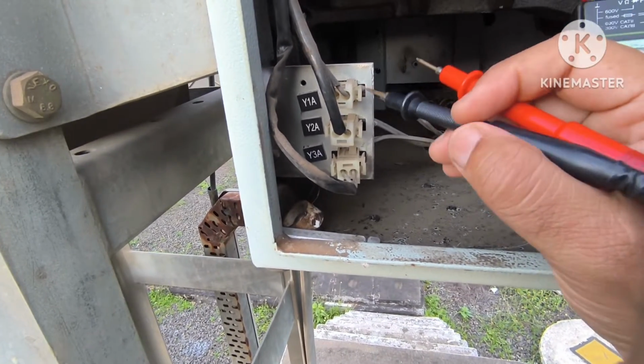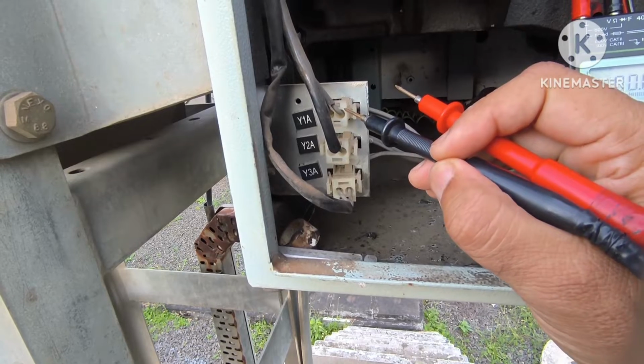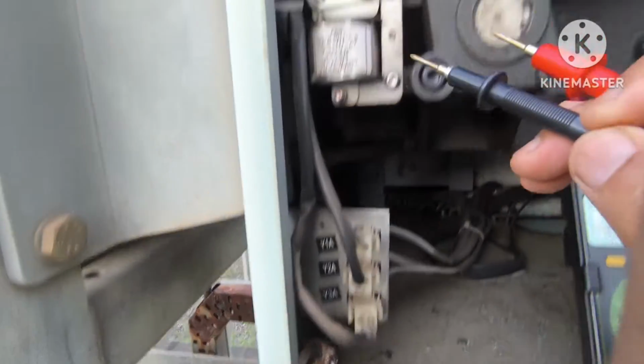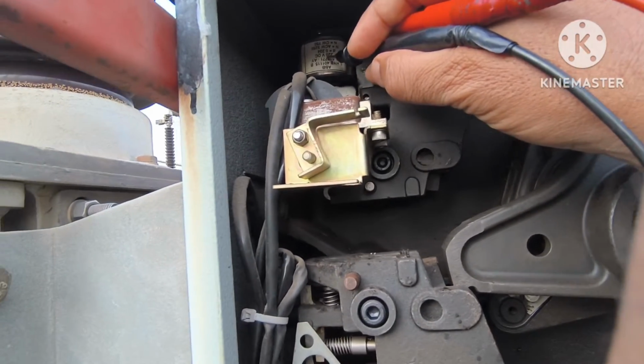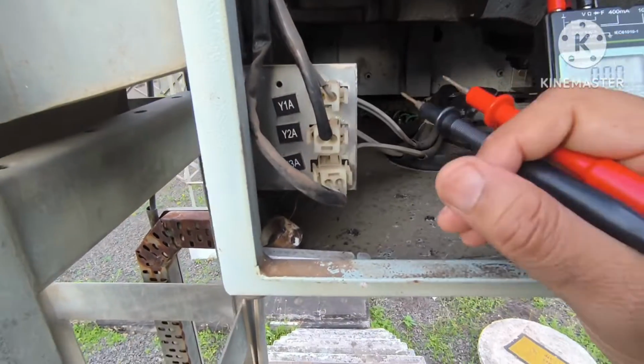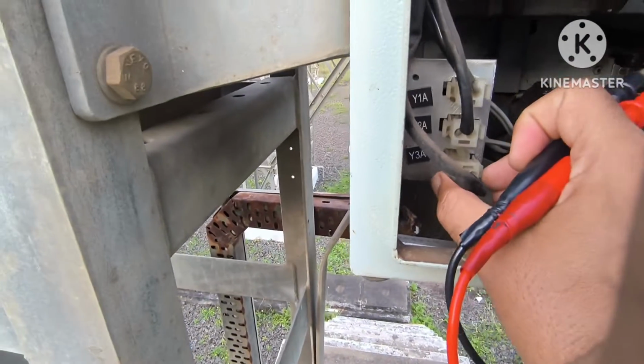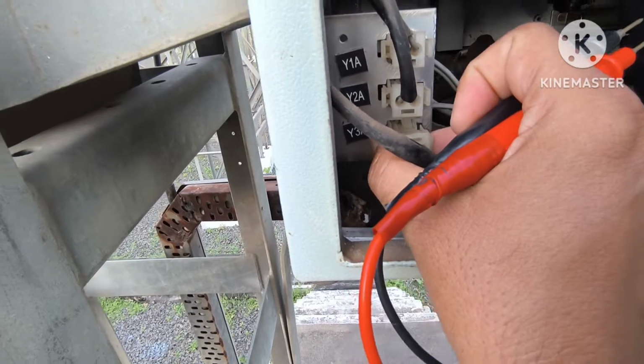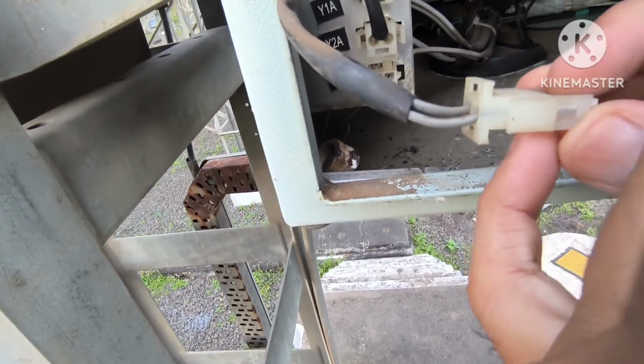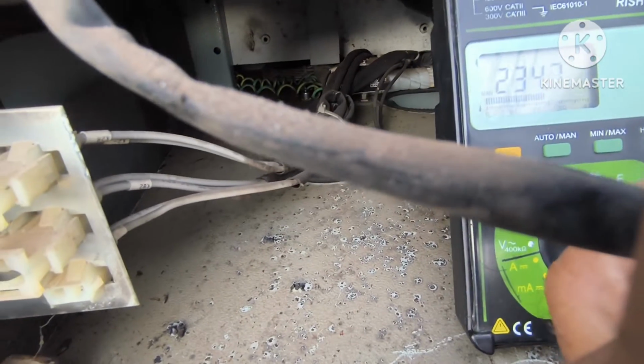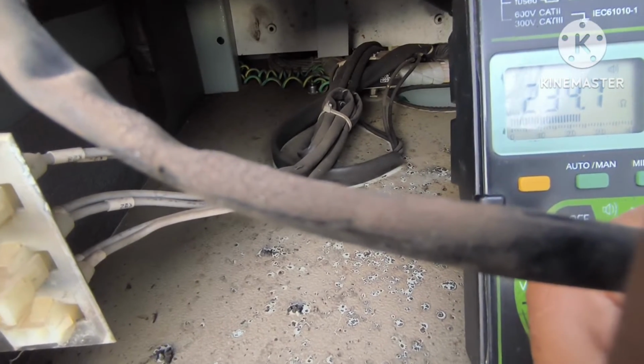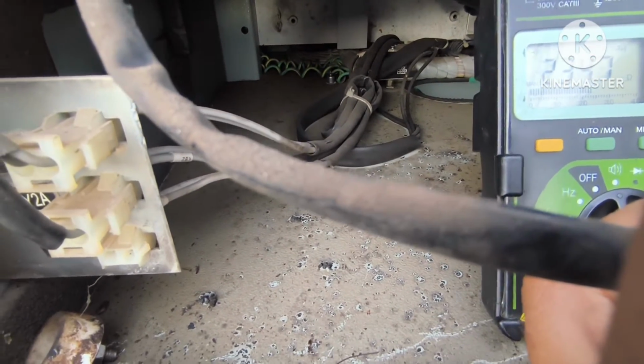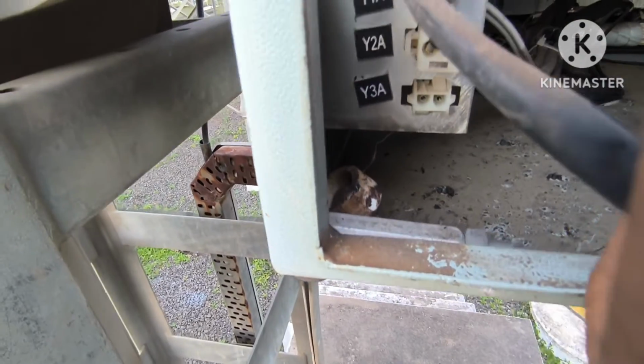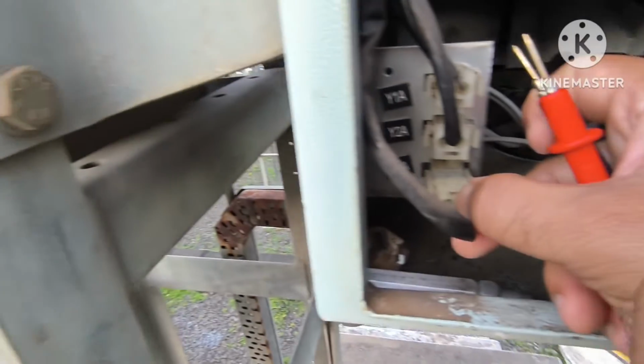To measure the coil resistance, we can measure directly here. This is the closing coil. This is trip coil 1, trip coil 2. So here you can see, this is trip coil 1, trip coil 2, and this is the closing coil. The resistance will be nearly 240 ohms. So I can open it like this. I open it like that, and you can see the resistance here. 234.7, nearly 240 ohms resistance will come. So like that, this is trip coil 2, trip coil 1 also we can measure.